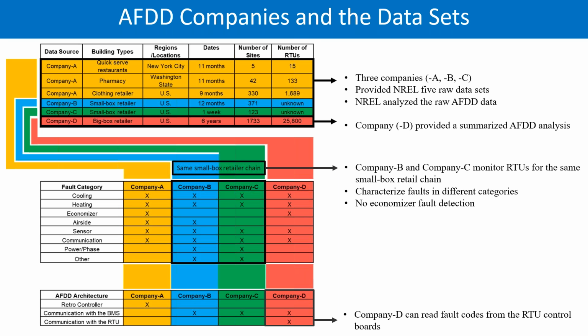This was our best opportunity to do an apples-to-apples comparison, despite the fact that Company C only provided 1 week of data and Company B provided 12 months of data. The bottom table shows the architecture of these systems. Company A has a retro controller type system that they use to detect and diagnose faults. Company B, C, and D all communicate with the BMS. In addition, Company D communicates with the control board of the RTU in order to extract error codes.